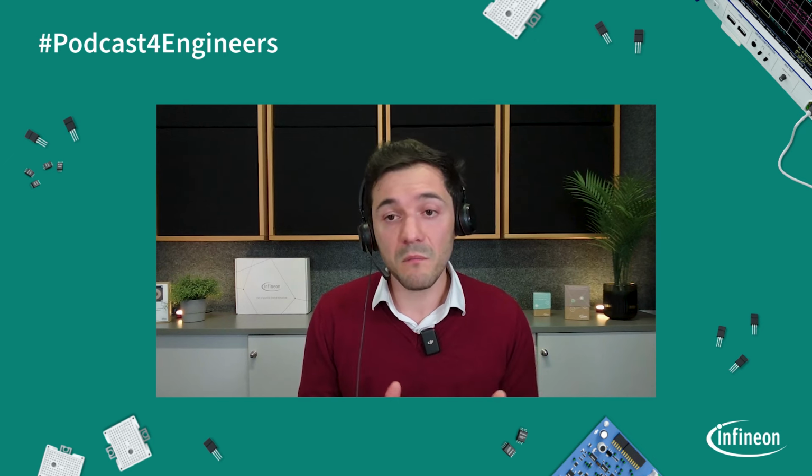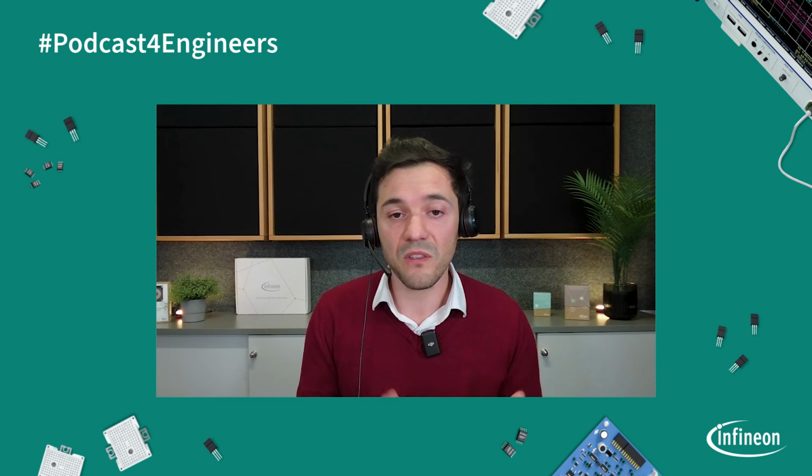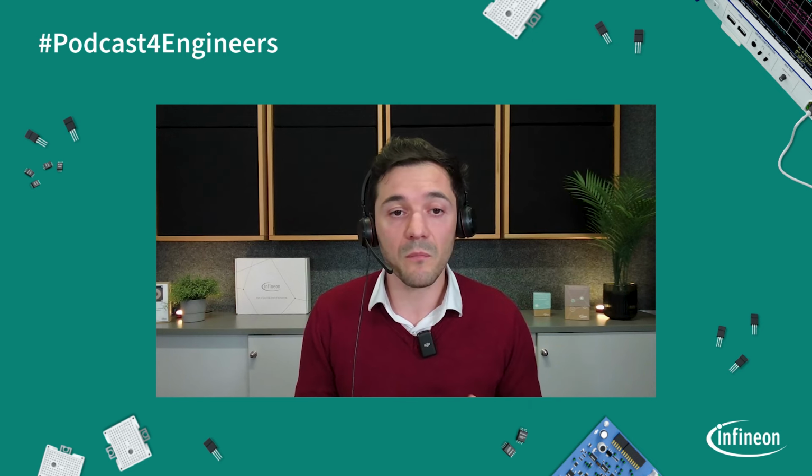Then let's move on to the first stage, which is called Intermediate Bus Converter, IBC. Here we need to reduce the losses of the intrinsic topology we have nowadays. For example, the state of the art is an LLC converter. Let's talk about, for example, the unregulated DCX converter. There are ways to reduce the current stress in both silicon and magnetics. And we came up with some ideas and also products on how to reduce those losses, and we'll deep dive later on.